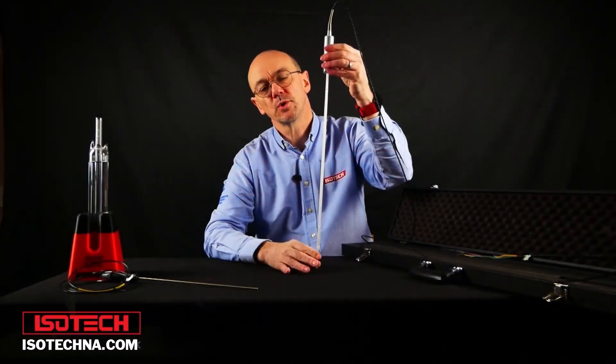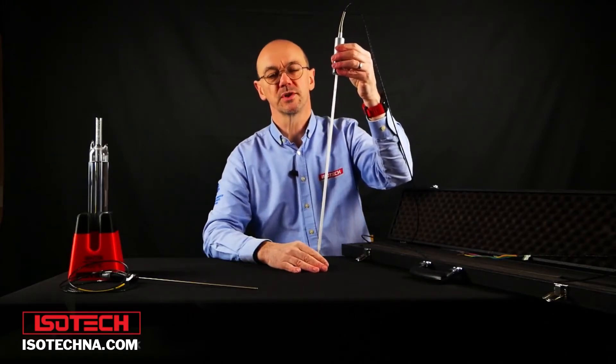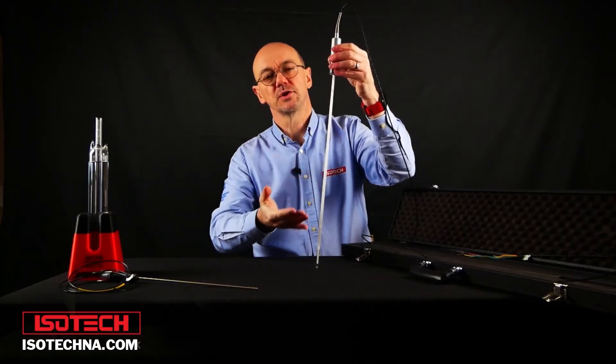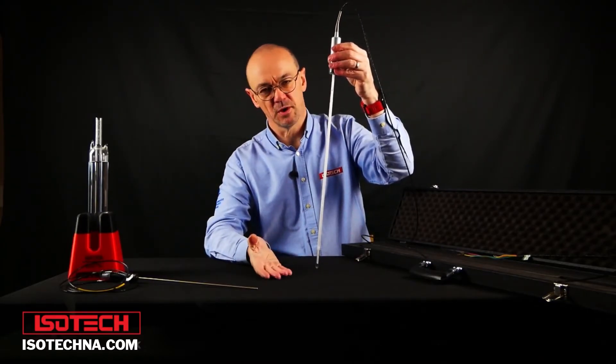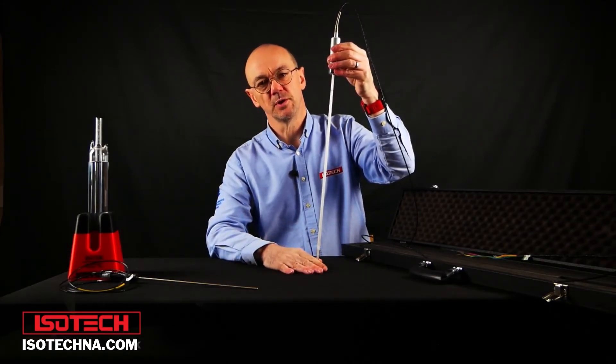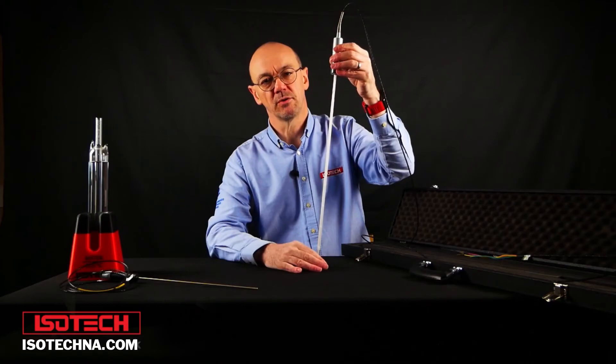At Isotech, we always point out that when you're using an SPRT, it's really important to consider the application. SPRTs need good immersion depth, and if you can't immerse the thermometer deeply enough, it's not the thermometer to use. These devices are very fragile — they're not suitable for use in industry or as portable instruments. They really belong in the calibration lab, where they can be handled very carefully.